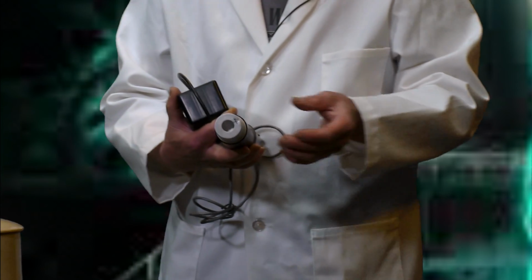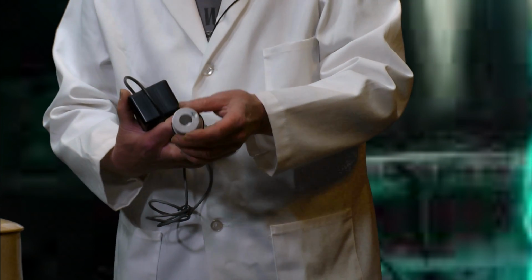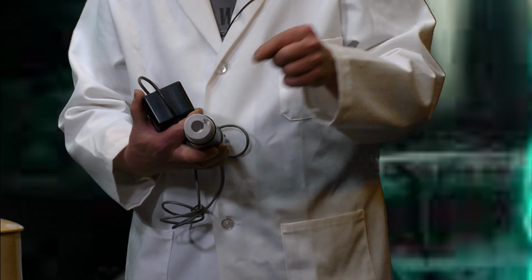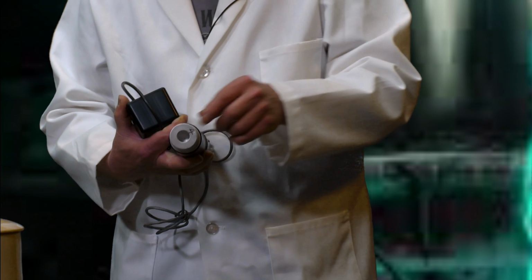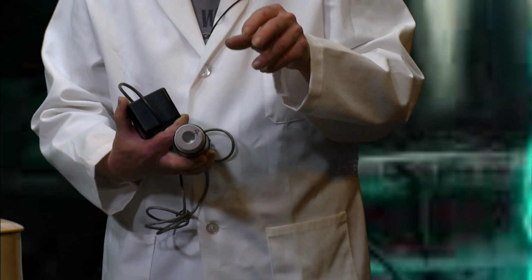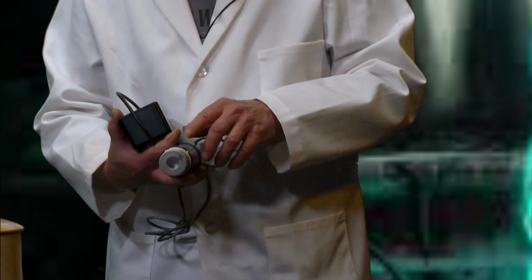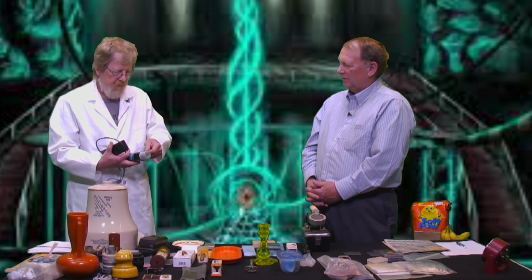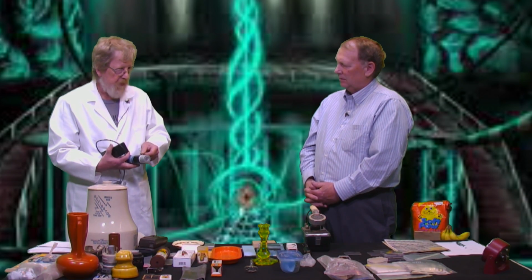So what happens is this. The crystal has a particular property: when a radioactive particle hits it, it scintillates. It puts out a brief flash of light. The photomultiplier tube, if you look at those two words, photo and multiplier, the flash of light comes into the tube and gets amplified, hence photomultiplier. But it's very, very sensitive and not for use with this type of stuff.